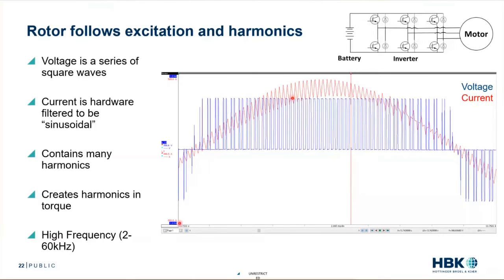Some of you might recognize that 2 kHz is absolutely in the audible range, and a decent amount of that switching frequency range is audible. So we have to consider that the inverter itself is going to produce some noise. This high-frequency current in the stator is also going to expand and contract the stator magnetically, producing additional noise — in addition to the noise caused by the harmonic torque. The magnet on the rotor is following that current on the stator, so we're following all those harmonics.